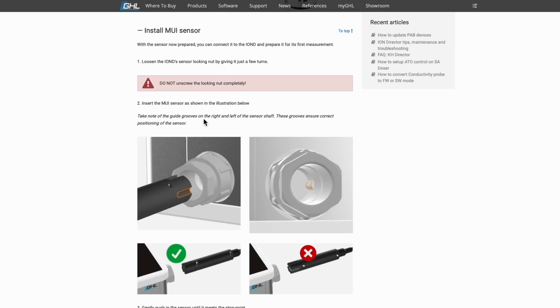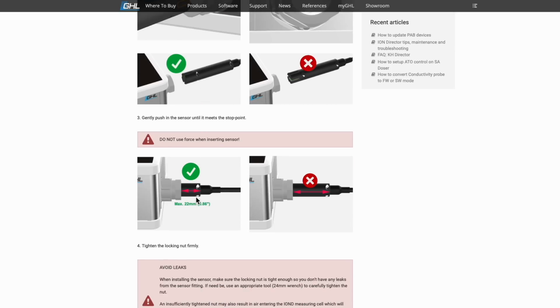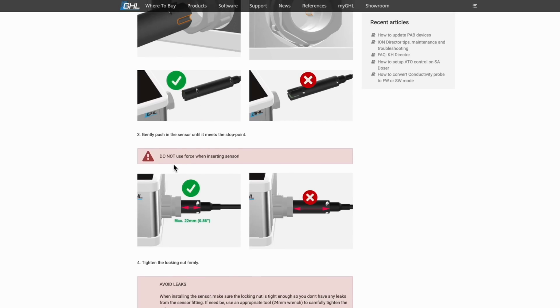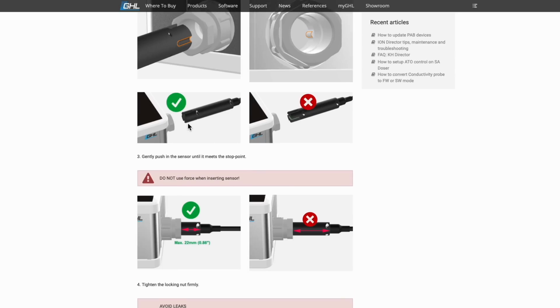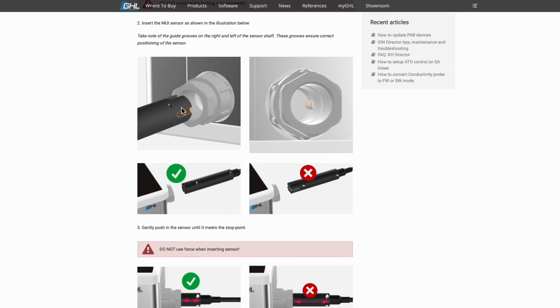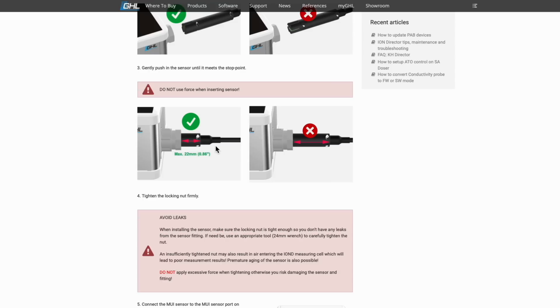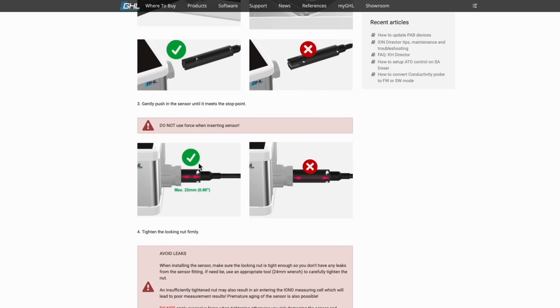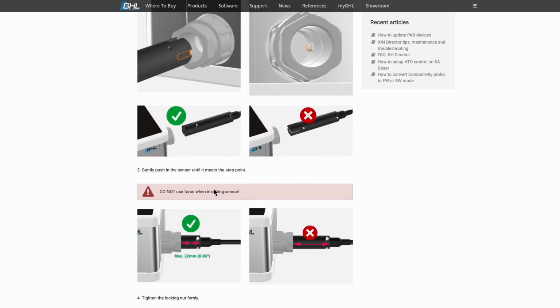Now this, again, I am grateful that they actually gave you this measurement here, because it says do not use force when inserting the sensor, and it's got a very precise way it has to go in. It's got these little notches which will line up in there. I actually installed it nice and gently, and was all good and well. And I went and measured it, and I was nowhere near 22 millimeters, so I had to actually push it in with a little bit of force.